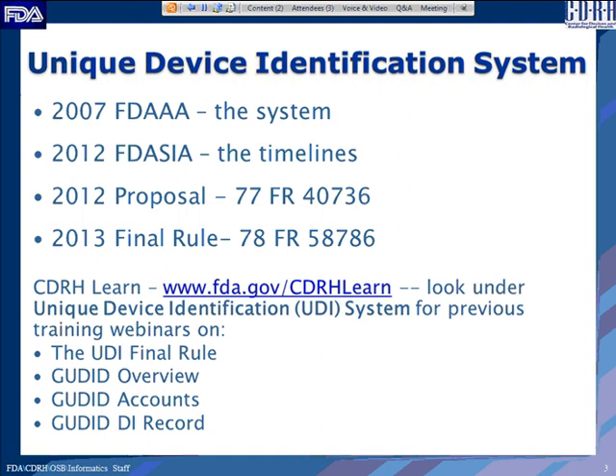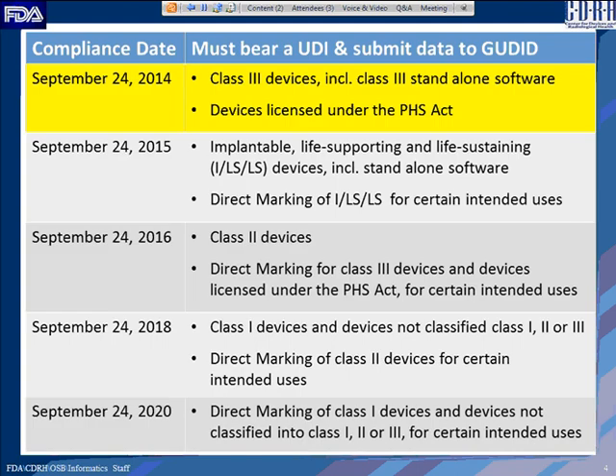This training module is best viewed sequentially after prior GUDID webinars. Compliance dates are all September 24th, running through 2016, then 2018 and 2020. The right-hand column shows the class of device that must bear a UDI on the label and submit data to GUDID. Our immediate focus is the first row — Class 3 devices and devices licensed under the Public Health Act, due to be submitted to GUDID by September 24th.